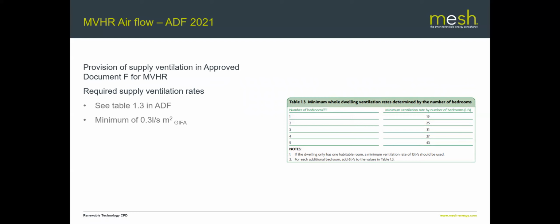So for a 5-bedroom house, where's that crossover going to be? Well, if we know 43 litres per second, divide that by 0.3, that would mean that for that first requirement to be the predominant one in a 5-bedroom house, we'd have to have a 5-bedroom house that was smaller than 143 1/3 metres squared. Well, I think if you've got a 5-bedroom house squeezed into 143 square metres, that's a pretty small requirement.